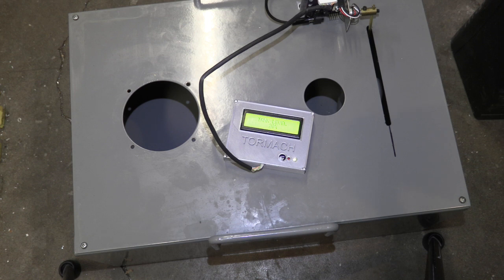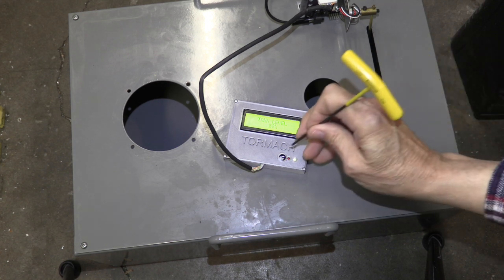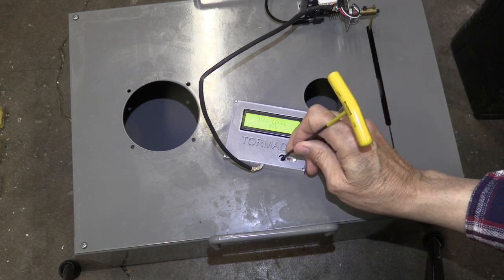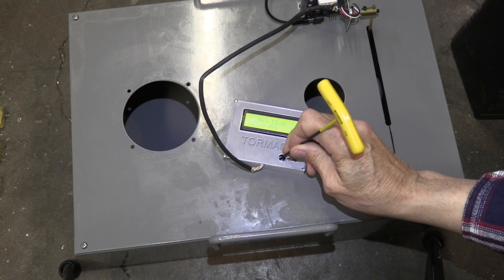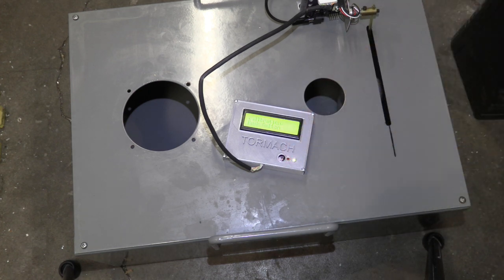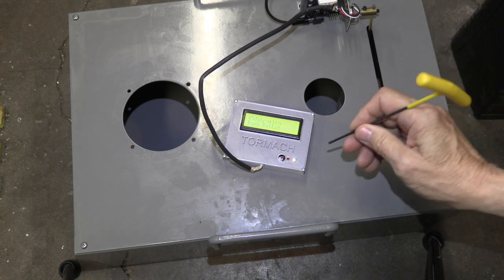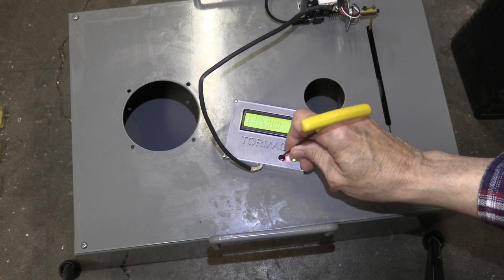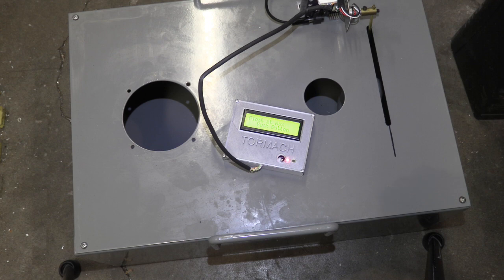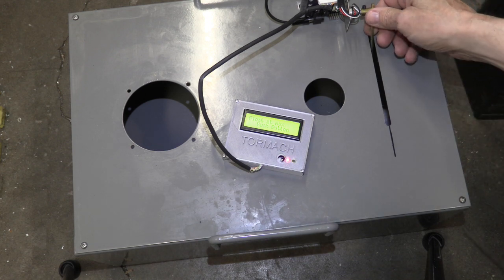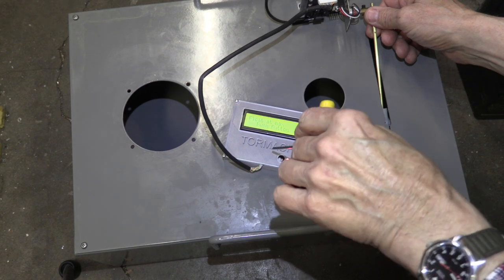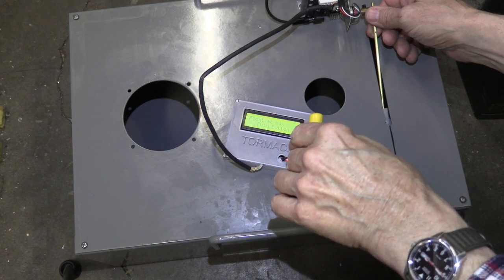Well, there's no coolant in the tank at all, and we just set this system up, so you can't expect it to be accurate, and that's the purpose of the calibration routine. And we enter the calibration routine by punching this little button here 3 times. And when we do that, the LEDs will begin to flash, and the display says go ahead and push the button again. So push that button again, and it's telling us to go ahead and set the float at maximum. This is measuring the maximum amount of water that can be in the tank, and when we do that, we push the button.